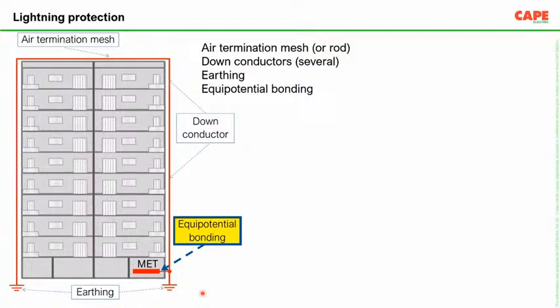Basically, external lightning protection is for protecting a building from a direct lightning strike. So you need to have an air termination, down conductor and earthing. Then the second part, electrical and electronic equipment plus the human beings inside the building. So electrical and electronic equipment in the installation is protected by making equipotential bonding. Equipotential bonding in the sense it is a protective equipotential bonding. There is main protective equipotential bonding, supplementary equipotential bonding, and you are supposed to have surge protection devices called SPDs.